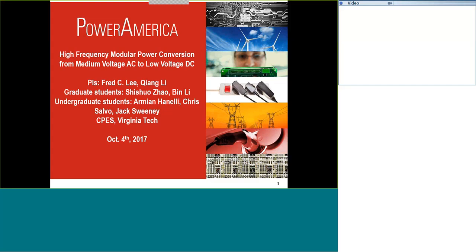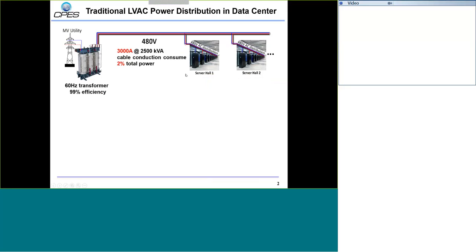This technology can be used for many different applications. Our main application is for the data center. This picture shows the conventional low-voltage AC power distribution in today's data center. Basically, medium voltage comes in, goes through a line-frequency transformer, then steps down to low-voltage AC — for example, 480 volt. People use this 480 volt to distribute inside the data center and then eventually go inside the server hall.